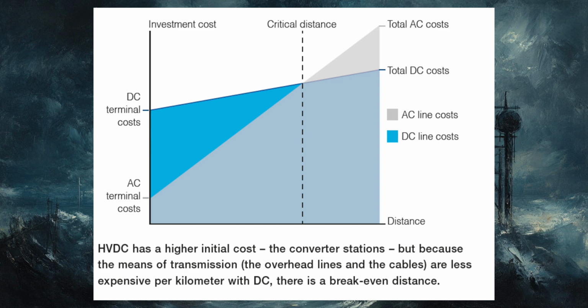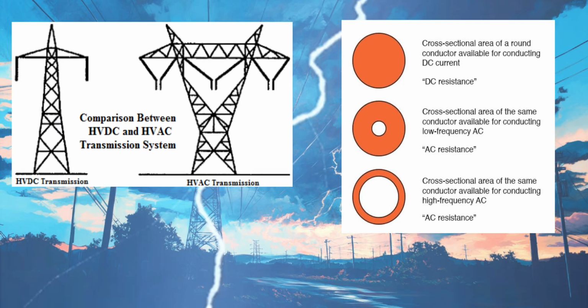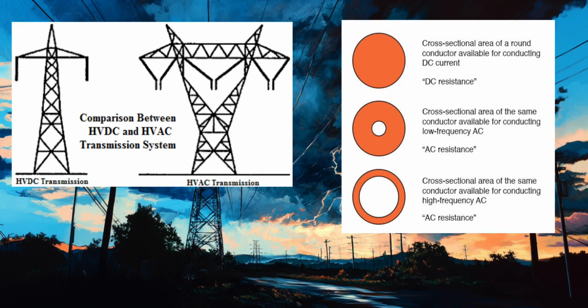There is a certain distance of transmission where AC becomes more expensive than DC. At the critical distance, the losses from the impedances in AC accumulate to the point that it becomes too expensive and inefficient to transmit AC power. For short distances, it is more cost-effective to utilize standard AC transmission, as developing the converters for DC has high initial costs. That is why HVDC is used for long-distance interconnection of large countries like the United States and China, and also for offshore wind transmission. As stated before, DC will conduct with less losses than AC due to the impedances of AC. There is also another cost and efficiency benefit to DC.